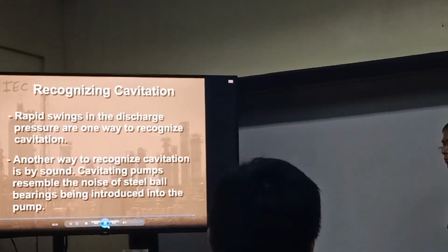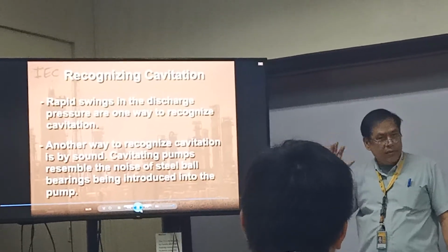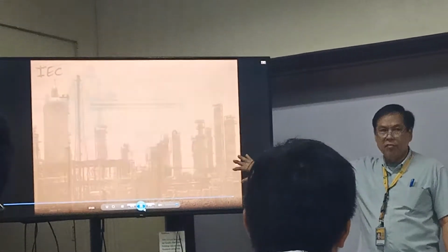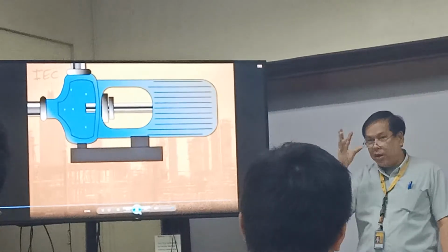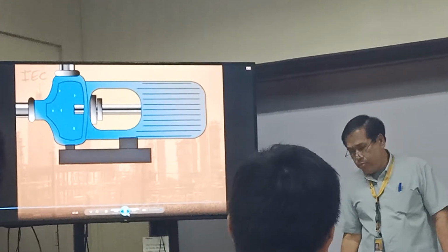Another way to recognize cavitation is by sound. Most common, maririnig nyo, cavitating pumps maingay. They resemble the noise of steel ball bearings being introduced into the pump. The tinging sound, yun yung mga cavitating bubbles. The problem must be resolved quickly in order to avoid severe damage.